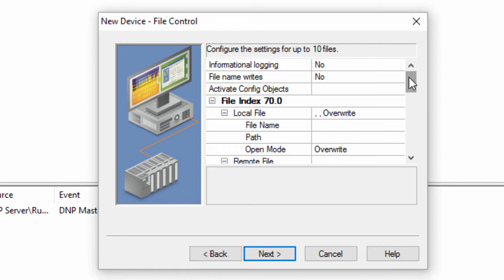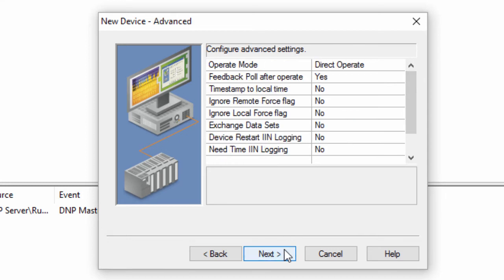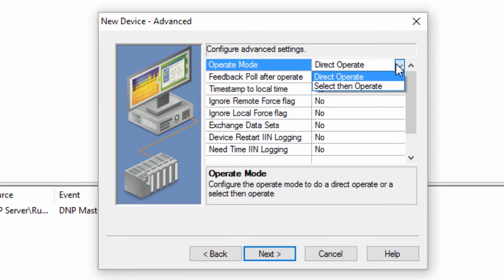Click Next to configure the advanced settings. The default operate mode defines how writes occur. There are two options: direct operate and select then operate. If your device has points defined as select then operate, you must first write a boolean true to the .so subtype for that point before writing to the value subtype of that point.